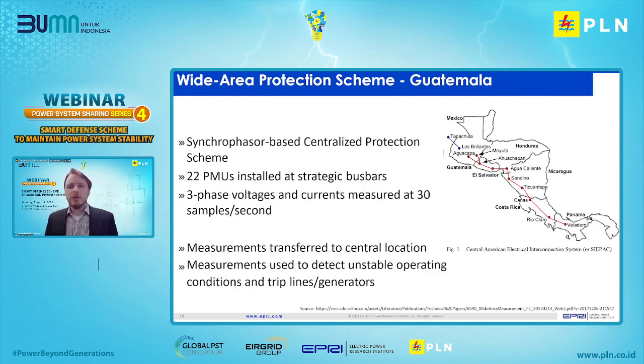Now, moving on to the more advanced schemes that are in operation now. In Guatemala and Costa Rica in Central America, they developed a synchrophasor-based centralized protection scheme. This involves 22 phasor measurement units installed in multiple countries in the backbone of this transmission grid. All of the PMUs measure 3-phase voltage and current, and they're measured at 30 samples per second.